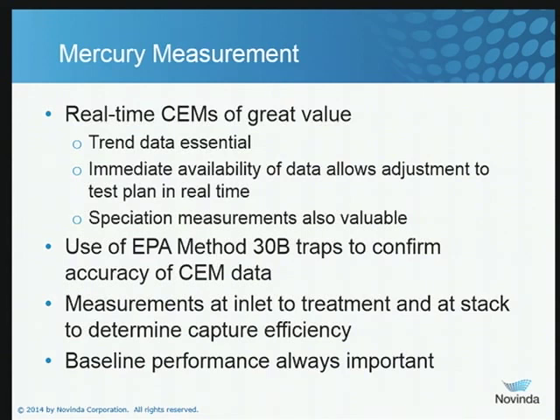Mercury measurements — as I have previously mentioned, real-time CEMS are something I'm a real believer in. There are a number of vendors that do a great job. They'll bring the system in, make sure it's calibrated, and keep it well maintained during a trial so you get quality data. The trend data is important and very useful. A CEMS gives us immediate feedback — real-time data. You can sit there and see if a condition is going to meet MATS or not. If it's not, you may do some tweaking to your test matrix in real time. For example, if two pounds per million ACF is not sufficient but four pounds per million ACF gets you down to half a pound per trillion BTU, you may go back and run a case at two and a half or three pounds per million ACF to see where that curve fits on an interpolation basis.